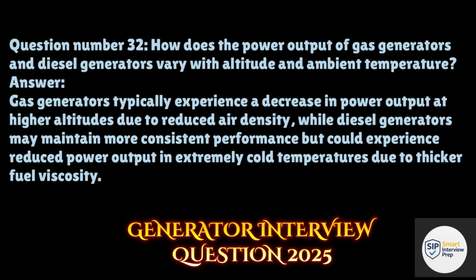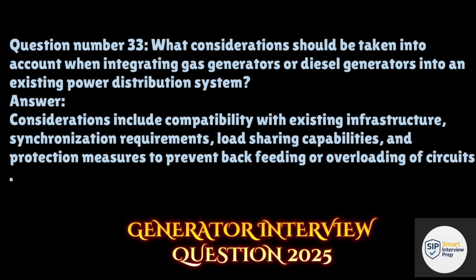Question 32: How does the power output of gas generators and diesel generators vary with altitude and ambient temperature? Answer: Gas generators typically experience a decrease in power output at higher altitudes due to reduced air density, while diesel generators may maintain more consistent performance but could experience reduced power output in extremely cold temperatures due to thicker fuel viscosity.